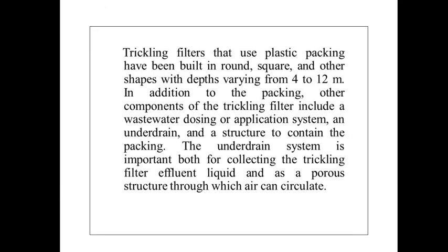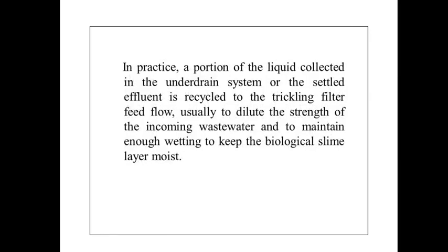The underdrain system is important both for collecting the trickling filter effluent liquid and as a porous structure through which air can circulate. Okay, so what is the application of the underdrain? The underdrain system is important for the collection of trickling filter effluent and also for the supply and circulation of air. In practice, a portion of the liquid collected in the underdrain system or the settled effluent is recycled to the trickling filter feed flow, usually to dilute the strength of incoming wastewater and to maintain enough wetting to keep the biological slime layer moist.